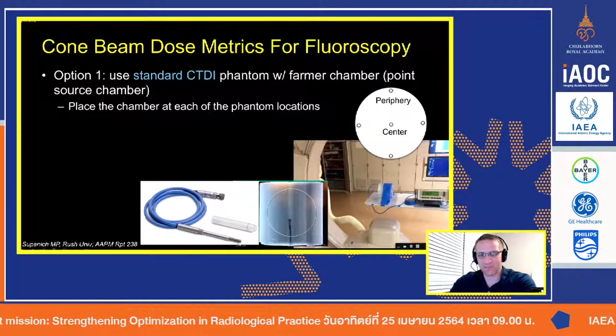We're going to place it at the center, and we're going to weight and multiply that by 1/3. Then we're going to make our measurements on all the peripheries. Every one of those will sum up, and we'll once again multiply that by 2/3. So we're doing the same kind of calculation, but it's not really CTDI, so be careful calling it that. You can go read some papers in the literature that will call this CTDI. It's not, so be careful what you call it. Some people, if you try to publish it and you call it CTDI, they won't let you publish it. So for what it's worth, you're mimicking the process of calculating CTDI.